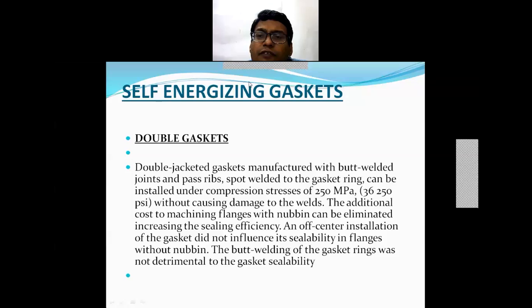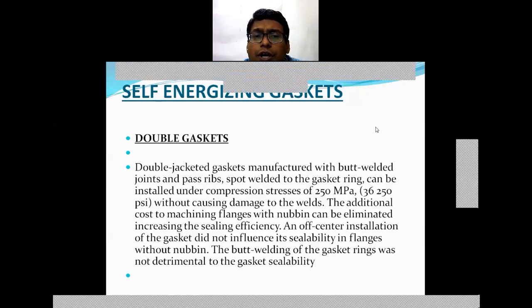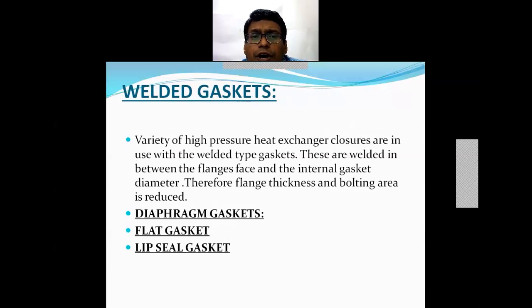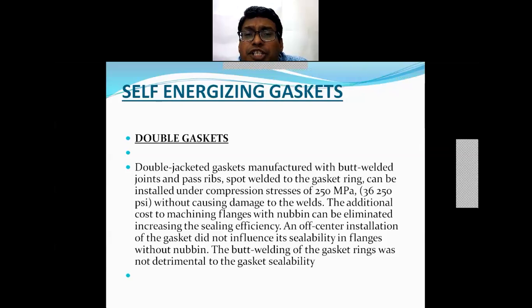So understanding self-energizing gaskets, these are the double gaskets, then delta gaskets, then lens type gaskets are the self-energizing gaskets. In this category, we have come across the gaskets in the pressure cooker. In the pressure cooker, as the pressure increases, these gaskets or the ring which is available in the gasket gets expanded and prevents its leakages. So this is the self-energizing gasket.